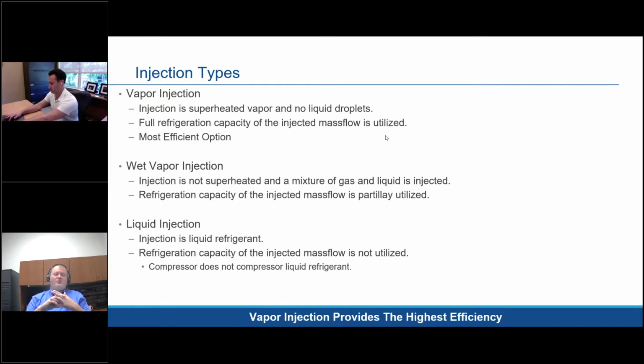And like I just went over, there's really 3 main injection types. Each has their own benefits. Vapor injection is the most efficient option, and the reason for that is you get a capacity increase by bringing that vapor refrigerant from the liquid line through a heat exchanger, which some people refer to as an economizer. It flashes it into a gas, and it comes back to the compressor, injected directly into the scrolls. What that injection does is it increases your mass flow, and it prevents the scrolls from overcompressing, and it allows the scrolls to use the entire scroll to actually move more mass flow into the condenser to get more heating capacity out of that. There is a power increase in that as well, but the capacity increase that you get outweighs that power consumption, and it greatly helps with the efficiency of that system.